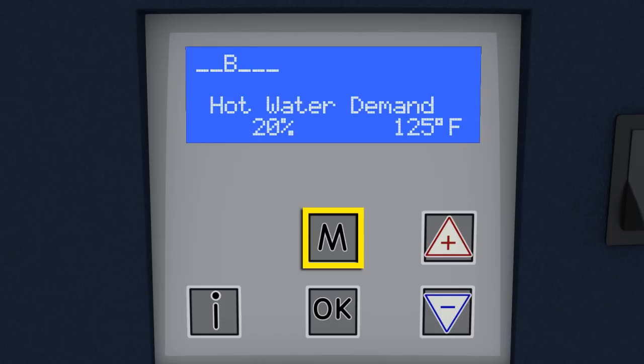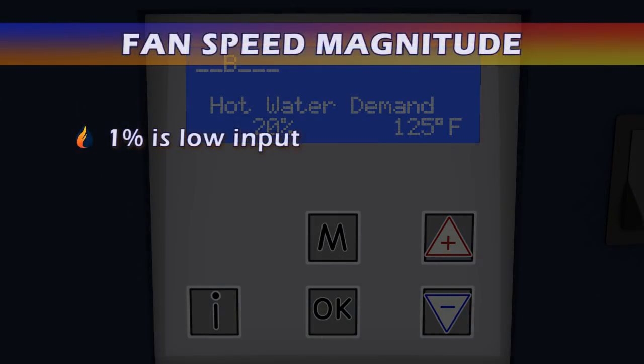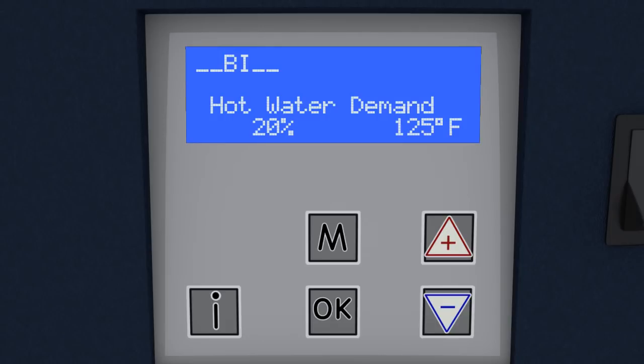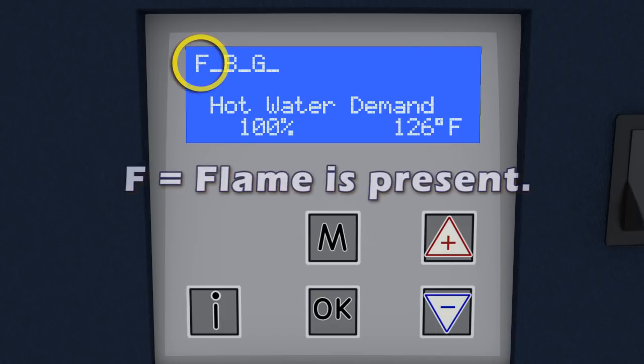The screen displays hot water demand if the set point was increased enough to start the ignition sequence. The percentage value that is displayed in the lower left corner of the screen is the magnitude of the fan speed. 1% is low input, 100% is high input. Letters indicating the status of the water heater are displayed in the upper left corner of the screen. They indicate when certain components are energized or actions are detected during the heating sequence.